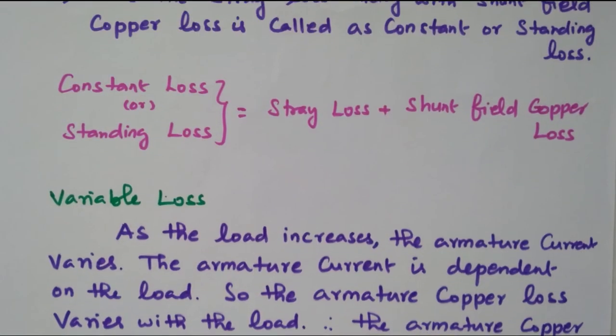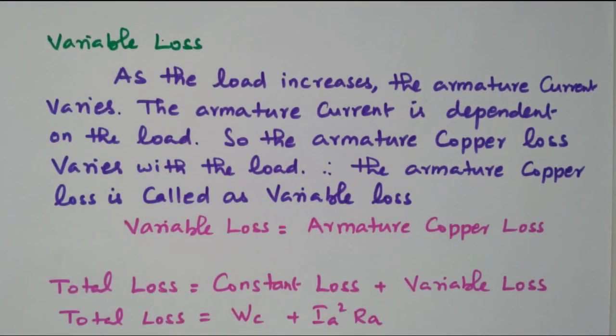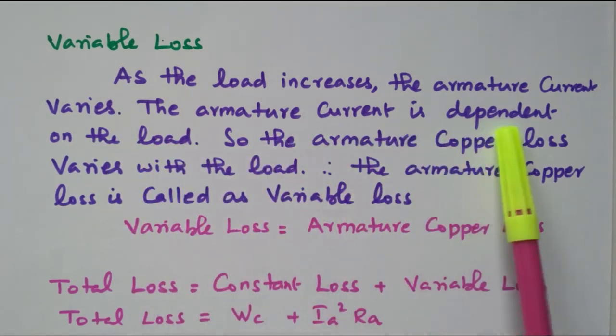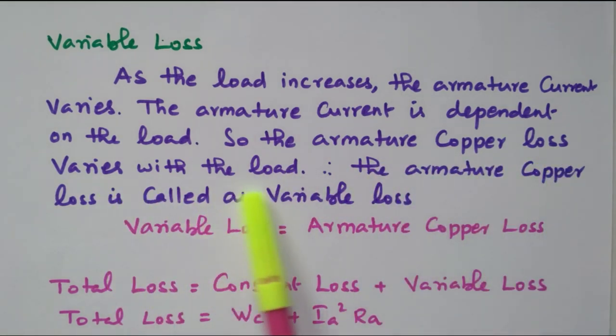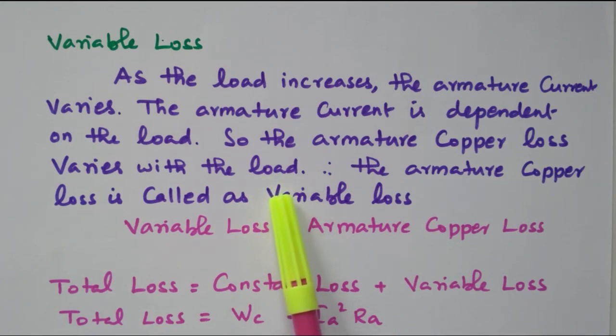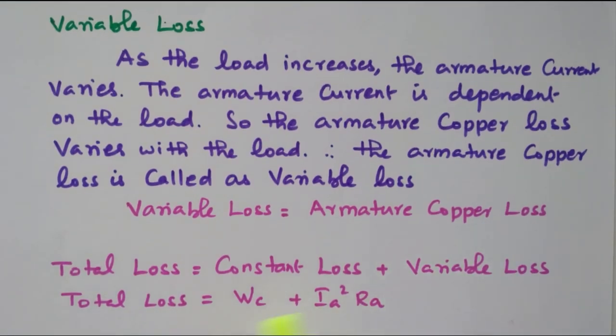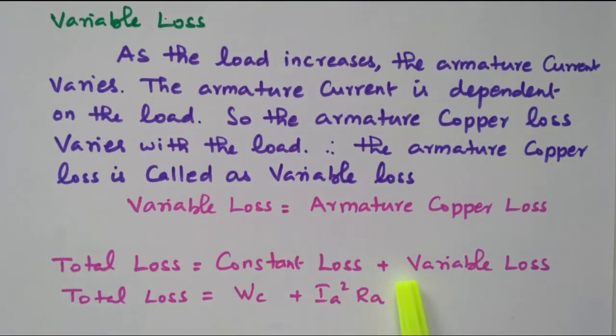Then we have variable loss. As the load increases, the armature current varies — it is dependent on the load. So the armature copper loss varies with the load, because Ia squared Ra: if armature current increases, the loss will also increase. Therefore, armature copper loss is called variable loss. All other losses are constant loss. That variable loss equals armature copper loss. So the total loss is nothing but constant loss plus variable loss, that is Wc plus Ia squared into Ra.